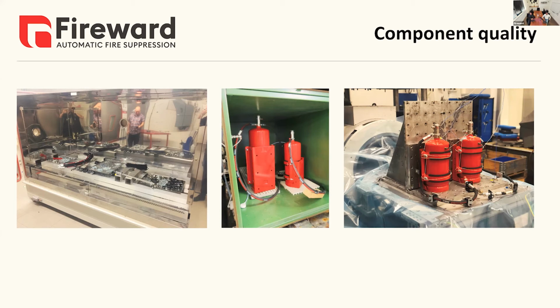After going through all that temperature cycling, corrosion, and vibration, you then need to discharge the system, and a certain amount must be released. I personally carried out the discharge testing — we discharged the entire 9 kilo cylinder apart from 6 grams of powder, which is incredible after 96 hours of vibration. This shows the system can take a huge amount of punishment, giving peace of mind when it's fitted on construction equipment — when it's called upon, it works.